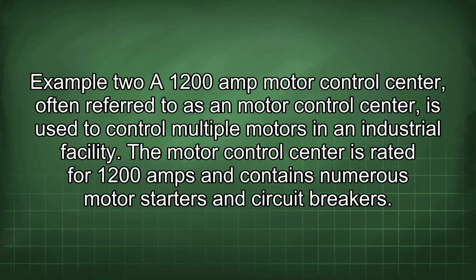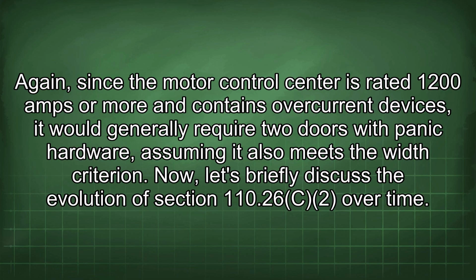Example 2: a 1200 amp motor control center is used to control multiple motors in an industrial facility. The motor control center is rated for 1200 amps and contains numerous motor starters and circuit breakers. Again, since the motor control center is rated 1200 amps or more and contains overcurrent devices, it would generally require two doors with panic hardware, assuming it also meets the width criterion.